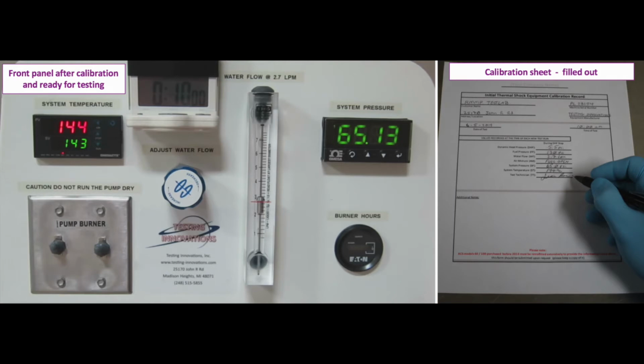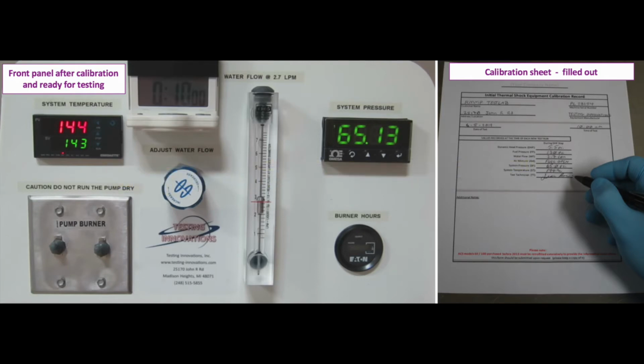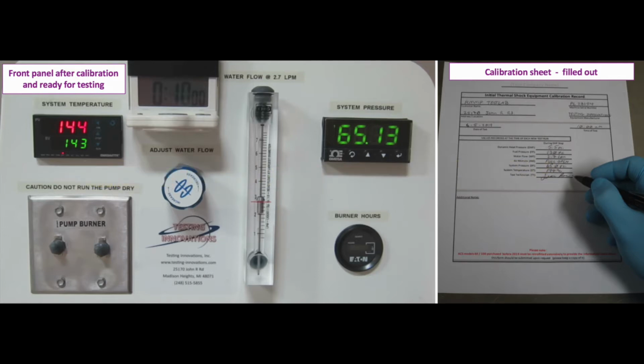Keep in mind the target values you are trying to maintain will drift. This drift will need to be dealt with. We have found that 1 or 2 degrees C of changing incoming water temperature will probably cause enough drift in the unit operating parameters to cause the water flow rate to rise out of tolerance. But how does a technician maintain the target values and control the fluctuations which we are calling drift?